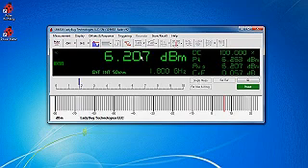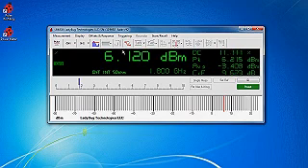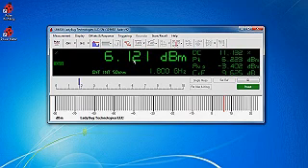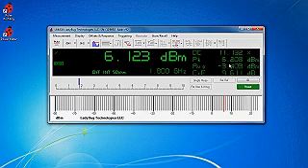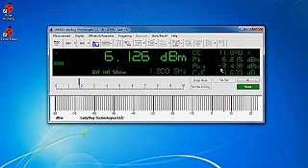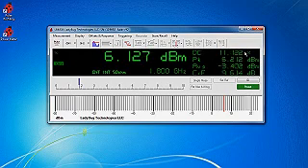We'll now switch the sensor to provide a pulse instead of a CW signal. So we're measuring the pulse power in the primary display. We're showing our average power. We're showing duty cycle, it's been measured for us by the sensor. We're displaying peak power. And we're also displaying crest factor.